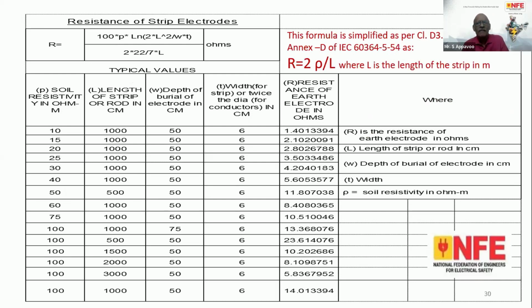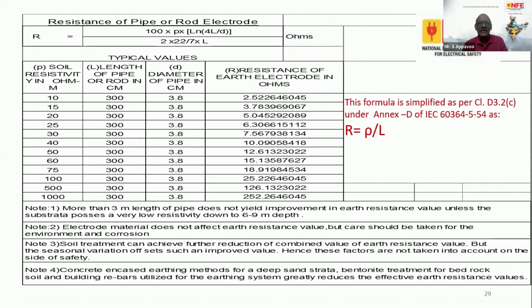This is simplified in the IEC 60364. You do not go into the rigorous calculation with allowable error. Of course, this gives you a factor of safety, even a stringent measure to calculate. You simply calculate the resistance of an electrode as twice the soil resistivity divided by the length of the conductor in the case of a strip electrode, and in the case of a rod electrode it is simply rho by L.